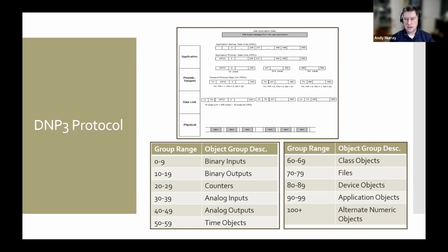The one thing about DNP that's different from Modbus is that Modbus is basically a poll and reply protocol. So the SCADA server would have to poll the device, and the device will send back its data. If the SCADA server doesn't send a message, the device would just sit there. DNP is a little bit different in that it has different ways that it can report data. It can do that poll and response, or it can do what they call polled report by exception, which is meant so that when you create the data points in the field device, you put them in groups in what we call classes. And you also set bands on them, or dead bands as they call them, where if this analog value goes up by more than 2 amps, then I want you to respond back. But if it doesn't go up by more than 2 amps, when the SCADA server asks for an update, you just say you have no update. And you can probably tell that these advantages of the protocol were more meant for when you were constrained with bandwidth.